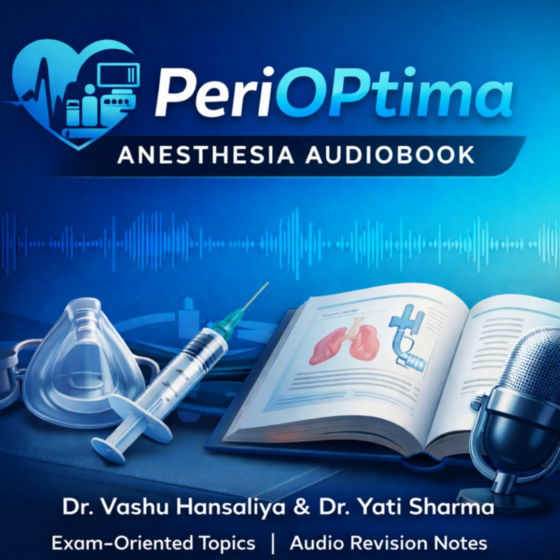The oxygen failure protection device, which is often just called the fail-safe, protects against a failure of supply pressure. So if the pipeline fails or the tank runs out. Exactly. It relies on a master and slave relationship. Oxygen pressure is the master. If your oxygen supply pressure drops, usually below about 30 psi, a valve automatically cuts off the flow of nitrous oxide. So it prevents you from giving 100% nitrous if the oxygen tank runs dry. Yes, but, and this is the huge caveat, it only detects pressure, not flow.